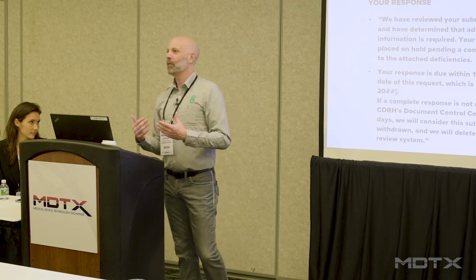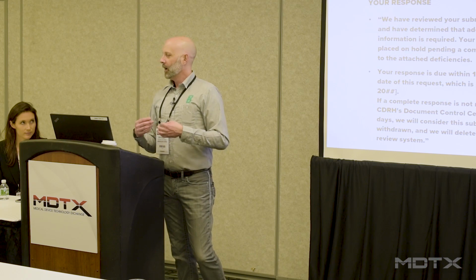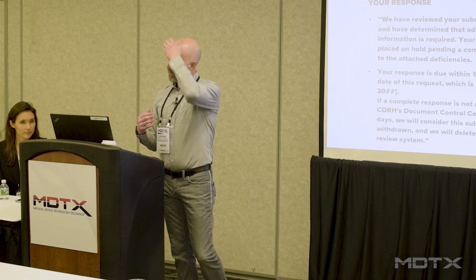The words do matter. Indications for use. Sometimes little words make a big difference. So if you have a very specific business reason for a little word that FDA is trying to get you to change, that's probably something to evaluate and to discuss. But there's probably a very specific reason why they're asking. As Juan Carlos said a moment ago, sometimes reviewers are trying to steer you towards 510K rather than de novo and that sort of thing. So try to understand the motivation behind that.